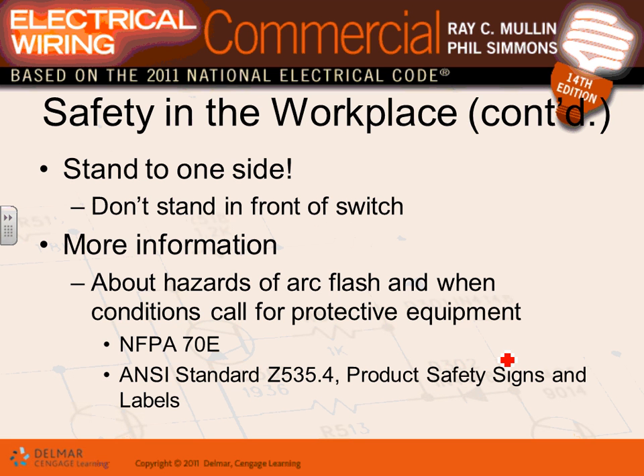This is a couple of things, guys, to be aware. Stand to one side. You guys are not working on energized equipment, but if you go in the field, and I've been in the field with electricians as an engineer, you make sure you move away. The rule is give yourself 10 feet away from any switch gear when they start working on it. That's the arc. There are examples where arcs have killed, so 10 feet, guys. When your electricians work on a panel and you're an engineer observing it, when they start opening that panel, move away 10 feet. That's your safety zone.